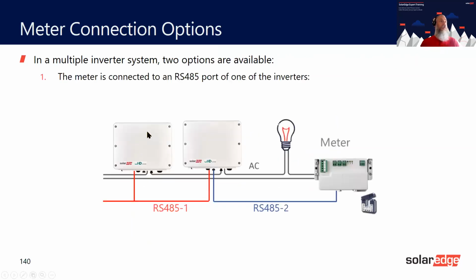If you have multiple inverters, don't worry, because remember on the communication board I showed you, it had RS485-1 and RS485-2. This allows you to use one bus for leader and followers and the other bus for meters. You can't have them on the same bus. They must be on separate buses.